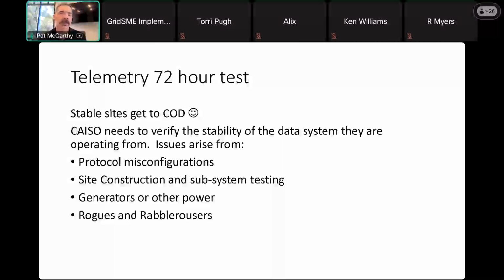And what the 72-hour test is looking at is every single device in that telemetry points list having 100% uptime for 3 days straight, consecutively. And if you can't achieve that, you're not ready to come into the market. So things that can cause problems there, obviously wireless. If you're using wireless as your communication path, cell phone tower outages and stuff, if it's a known outage, you might be able to get a pass from CAISO. If you have bad data continuity or just low bandwidth or something that's causing frequent drops in your data, you're not going to get approved to come online with that data path.